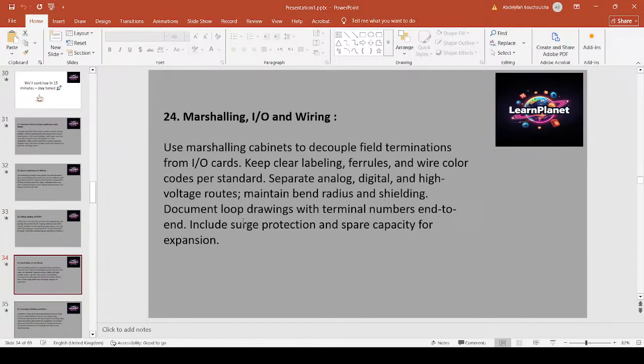Marshalling, I/O and wiring. Use marshalling cabinets to decouple field terminations from I/O cards. Keep clear labeling, ferrules, and wire color codes per standard. Separate analog, digital, and high voltage routes. Maintain bend radius and shielding. Document loop drawings with terminal numbers end to end. Include surge protection and spare capacity for expansion.